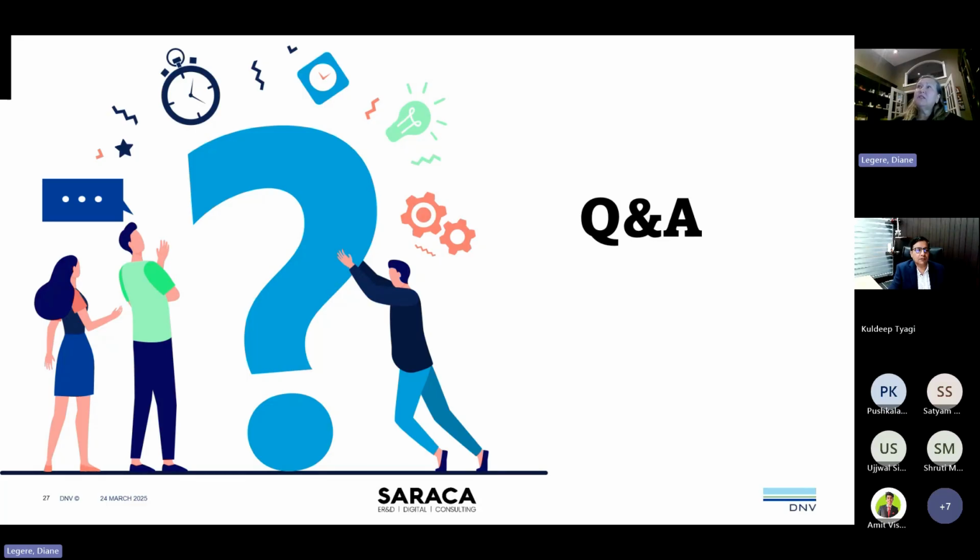Sometimes I've seen companies actually test that device themselves for the biologic, so they can meet that part if they need to. But go and read that part of the MDCG, and you'll see that it's clearly stated there. You just have to have a sufficient level of access. That's hard to define depending on your device, but a contract is not absolutely necessary. I'll just say that.